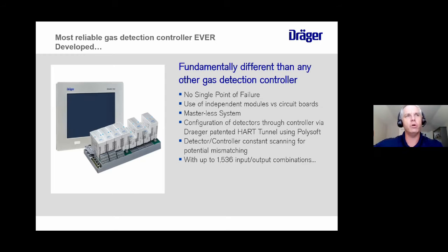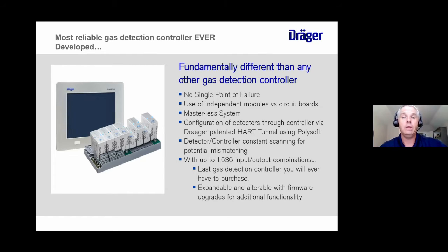And so with our system, you can have up to 1,536 input and output combinations. Basically you can have a Regard system with up to 8 docking stations and 8 modules per docking station. You can have a really big controller, so it's almost infinite with 1,500 inputs and outputs. And what I like to tell folks is that it's the last gas detection controller you'll ever have to purchase, because we made it expandable and alterable with firmware upgrades for additional functionality.